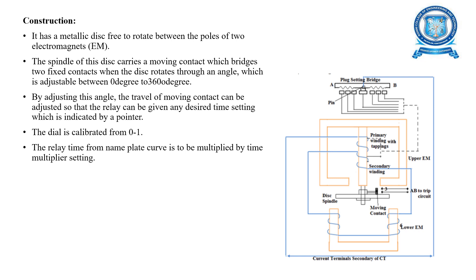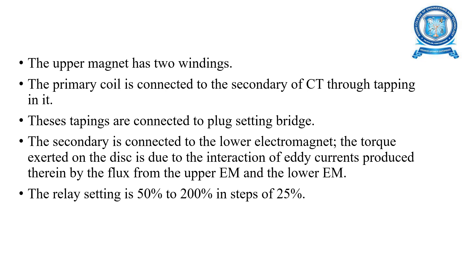Regarding construction, there is a metallic disc free to rotate between the poles of two electromagnets, as shown in the diagram. The spindle of this disc carries a moving contact which bridges two fixed contacts when the disc rotates through an adjustable angle between 0 and 360 degrees. By adjusting this angle, the travel of the moving contact can be set, giving any desired time setting indicated by the pointer. The dial is calibrated from 0 to 1. The upper magnet has two windings; the primary coil is connected to the secondary of the current transformer through tapping, and the secondary is connected to the lower electromagnet. The relay setting is 50% to 200% in steps of 25%.